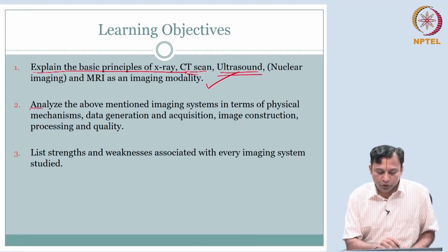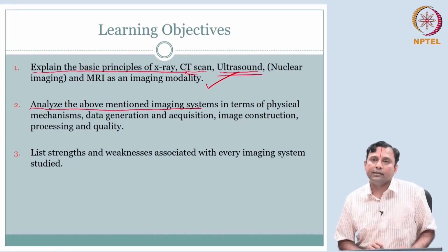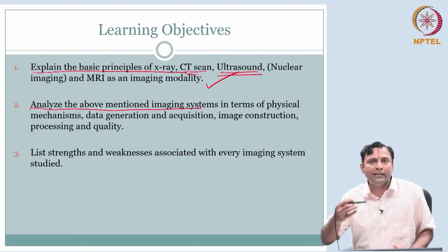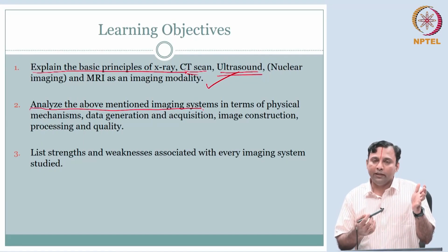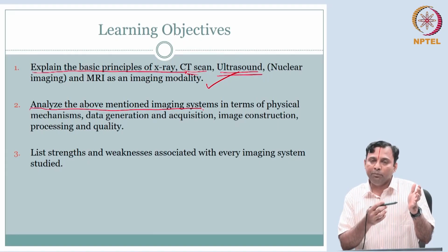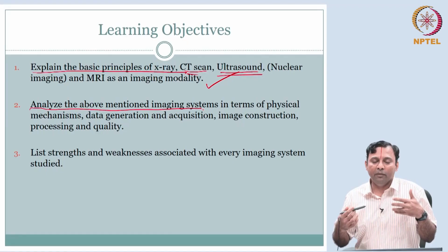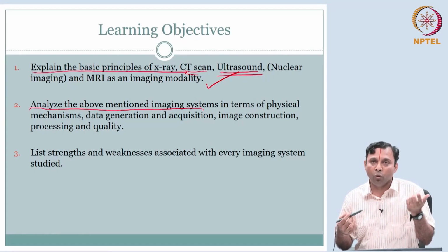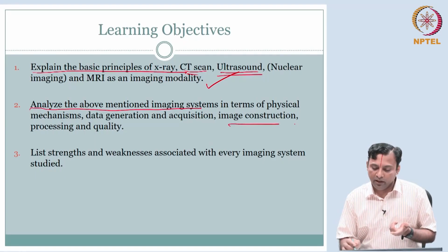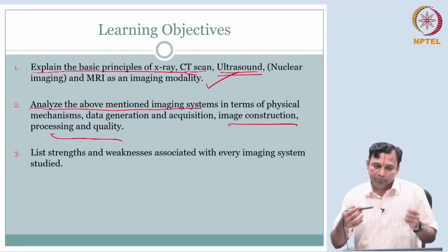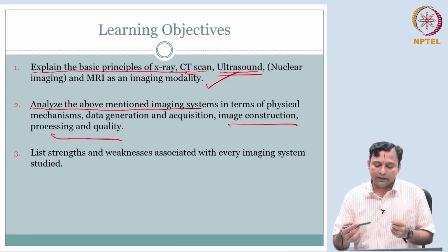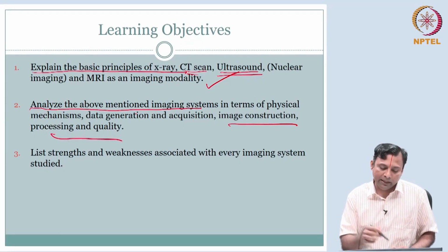To some extent, you should be able to analyze the system. When I say analyze, it is not analyzing the image. It is analyzing the system. What do we mean by analyzing the system? Is the image showing poor quality? Is there a dropout? Is it because the patient himself biologically does not have the signal there, or because the instrument probe is gone, or because of software? Any of that. So you should be able to analyze the output and understand the system and system settings that give rise to the image.